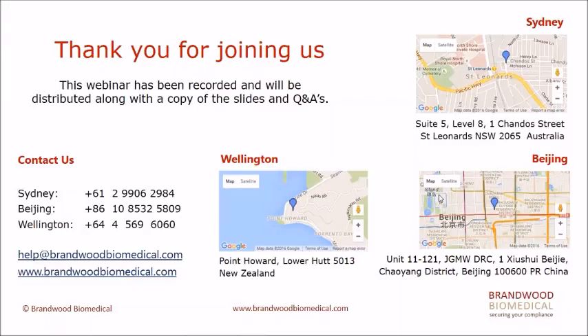Rob says, I hear the use of the term state-of-the-art in both the medical device directives and the medical device regulations. What's a standardized definition of state-of-the-art for a device or a software, whatever? That's a very good question, Rob. The conventional answer is a standardized definition. You don't realize the irony of what you said. You're closer than you think. It's essentially state-of-the-art as reflected in current consensus standards. So ISO and European standards reflect the state-of-the-art. So if you have a product standard, that's considered to be the current state of the art.